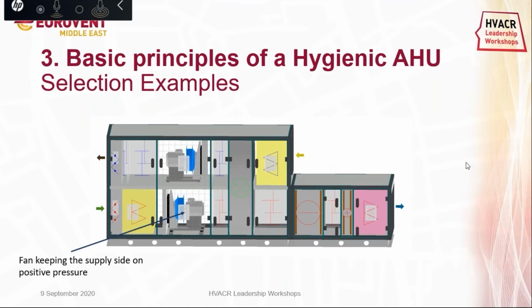Now let me present some hygienic AHU selection examples, also explaining the EATR concept on the unit as well. EATR is, as explained before, the air going from extract to supply, from here to here, through the rotary wheel sealing as a leakage or in the storage matrix of the rotary wheel, which is known as carryover. This means that the outdoor air to be supplied to the hospital is contaminated by the return air, the extract air, which must be prevented or kept at minimum levels. So how can we secure it is already explained.